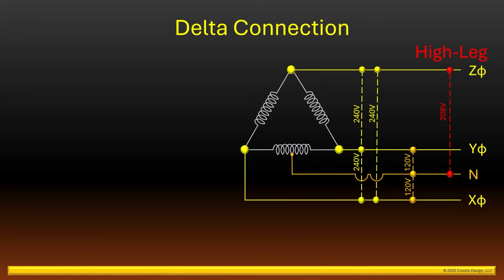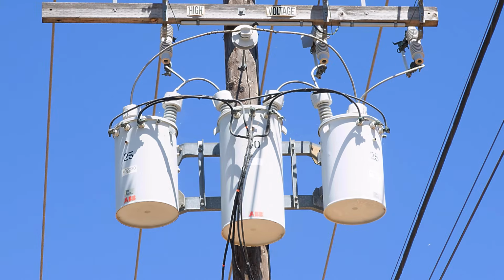Before we conclude, it's important to point out that single-phase 120 volts is only created in the winding of the center transformer. Single-phase 240 volts can be utilized from any one of the windings. Because of this, it's important to balance the single-phase load across all of the windings as much as possible. When a lot of 120 volt load is present, it may be necessary to install a larger center transformer to handle the excessive load. You may have noticed in this image, the transformer in the middle is larger than the other two for exactly that reason.